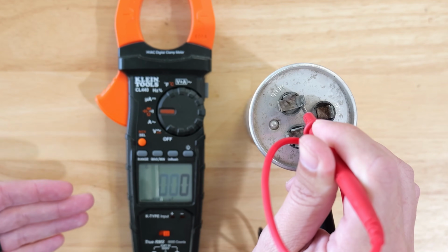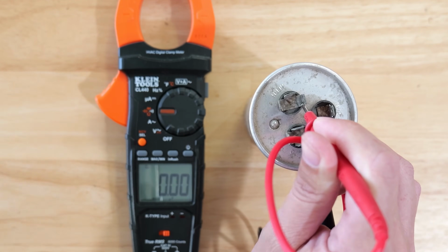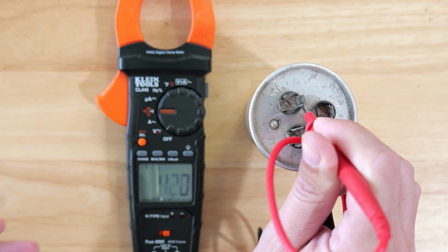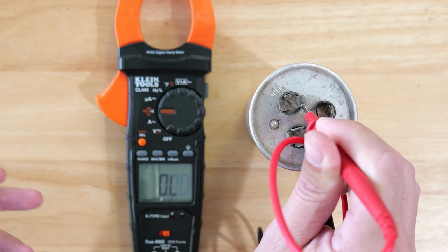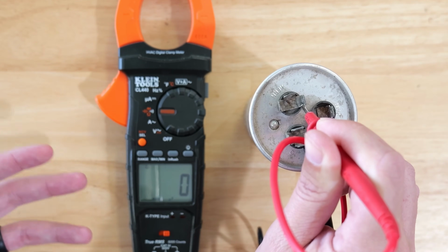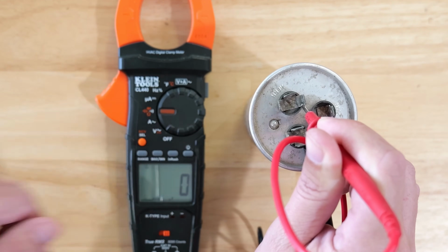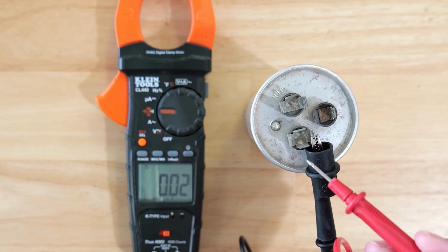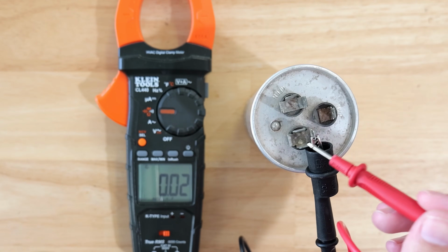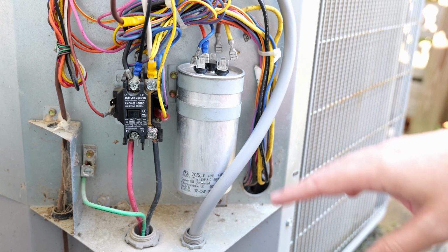Eventually this is going to settle on, it's going to show OL, which in a lot of multimeters means that it's over limit, which means in most cases that we don't have a good connection. But at the end of the day, it definitely means that this capacitor is bad. So it was bad going from the common to the fan, and it was definitely bad going from the common to the Herm.